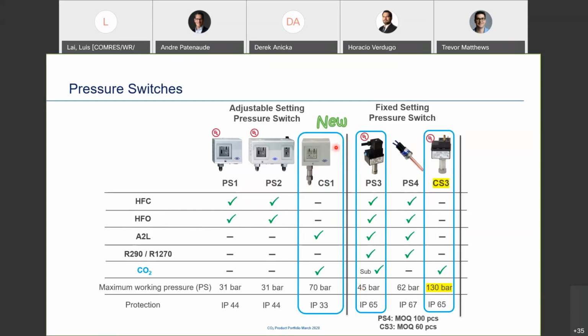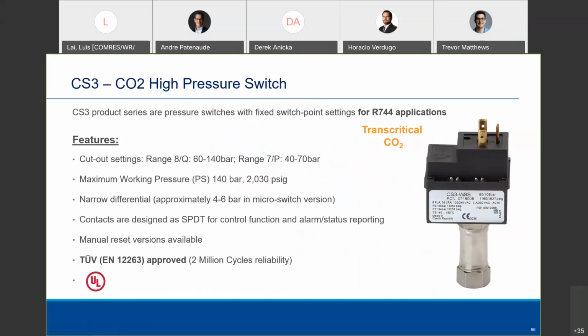This is designed for CO2, but not yet UL approved. The Europeans have just started selling it. It's basically taking the bellows arrangement from the CS3 and incorporating it into the design of the standard adjustable pressure control. So that's what we've done, but still not UL approved here for North America. So CS3, I talked about that. It's actually 140 bar rated.